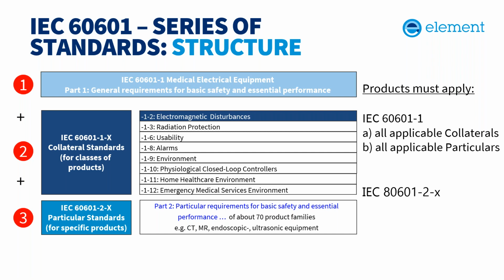The -2s are particular standards. They're for specific product types like ultrasonic devices, pulse oximeters, things like that. Also be aware that you might see 80601 standards. These are standards that are created in collaboration between IEC and ISO, but they're basically the same concept. They're focused on medical and they're particular standards. So you might see 80601-2-47. And with the structure of 60601, all products need to apply any applicable -1-X collateral standards, and for any electronic devices, that means 60601-1-2 in particular. -1-2 is the EMC standard for medical devices.